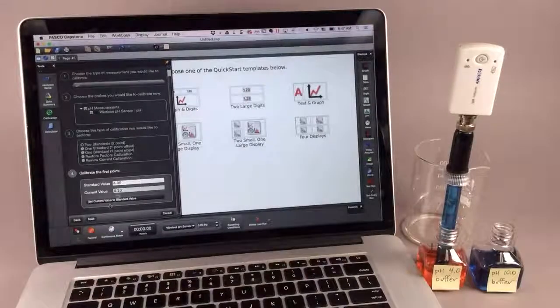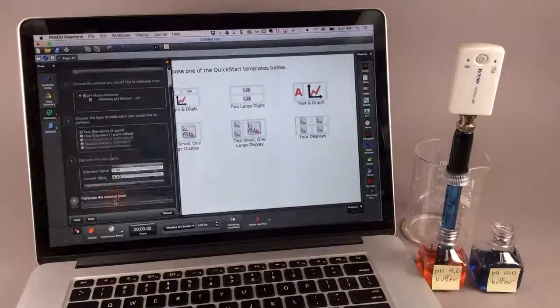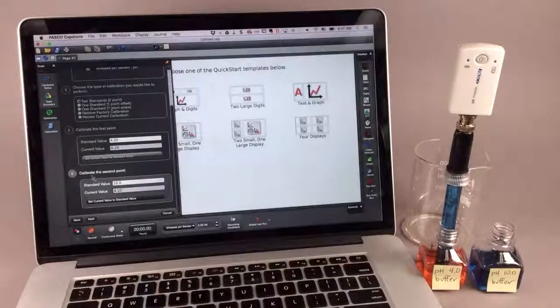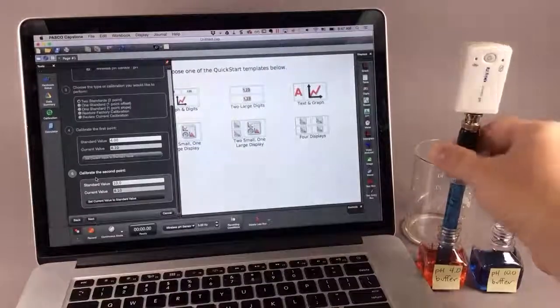And I'll wait till it stabilizes. This is the current value being read live from the sensor. Once it's fairly stable, I'll go ahead and press this button labeled Set Current Value to Standard Value. I can now proceed to calibrate the second point.